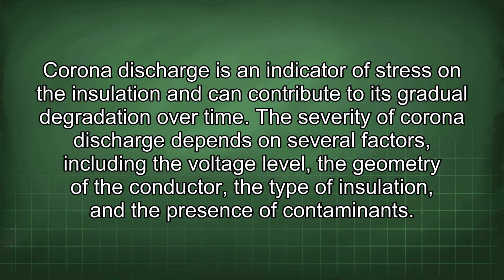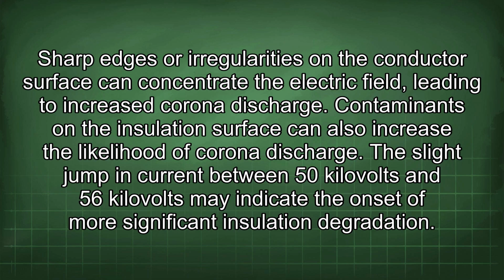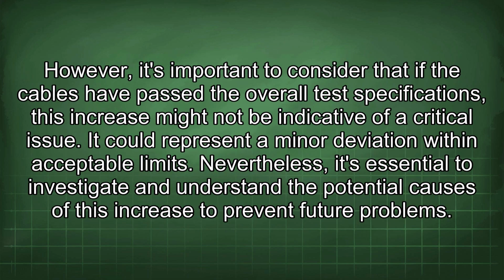The severity of corona discharge depends on several factors, including the voltage level, the geometry of the conductor, the type of insulation, and the presence of contaminants. Sharp edges or irregularities in the conductor surface can concentrate the electric field, leading to increased corona discharge. Contaminants on the insulation surface can also increase the likelihood of corona discharge. The slight jump in current between 50 kV and 56 kV may indicate the onset of more significant insulation degradation. However, it's important to consider that if the cables have passed the overall test specifications, this increase might not be indicative of a critical issue. It could represent a minor deviation within acceptable limits. Nevertheless, it's essential to investigate and understand the potential causes of this increase to prevent future problems.